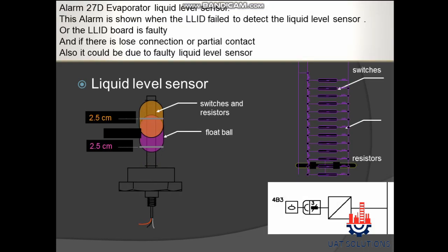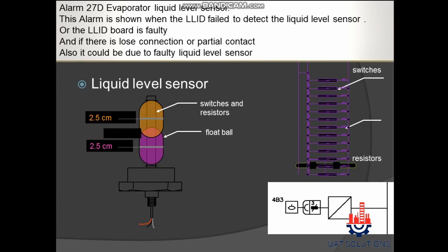Alarm 27D — Evaporator Liquid Level Sensor: This alarm is shown when the LLID fails to detect the liquid level sensor, or the LLID board is faulty. It can also occur if there is a loose connection or partial contact, or if the liquid level sensor itself is faulty.